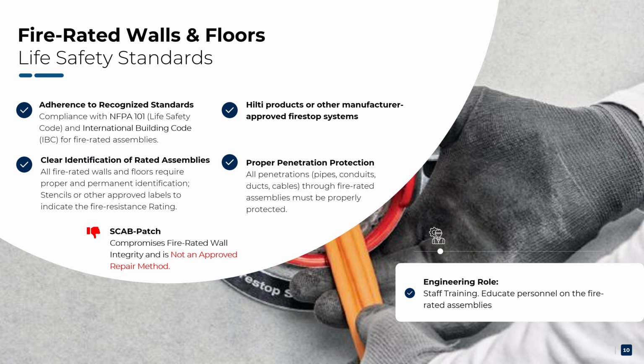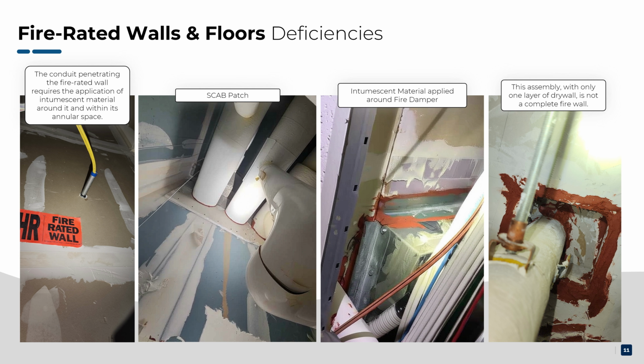You've mentioned fire-rated walls. Those are protecting us in case of fire, slowing the spread of fire and smoke. Exactly. And they're a vital part of building safety. That's why we need to ensure they're not only properly identified, but also correctly protected with approved fire-stopping materials. Let's look at some examples. Sure. Here we see a conduit penetrating a fire-rated wall with missing intumescent material around it and within its annular space. Intumescent. That's the material that expands in the event of a fire, right?